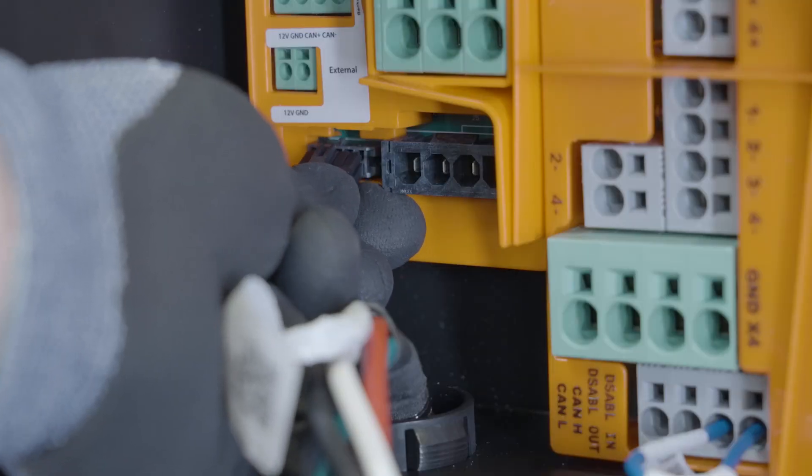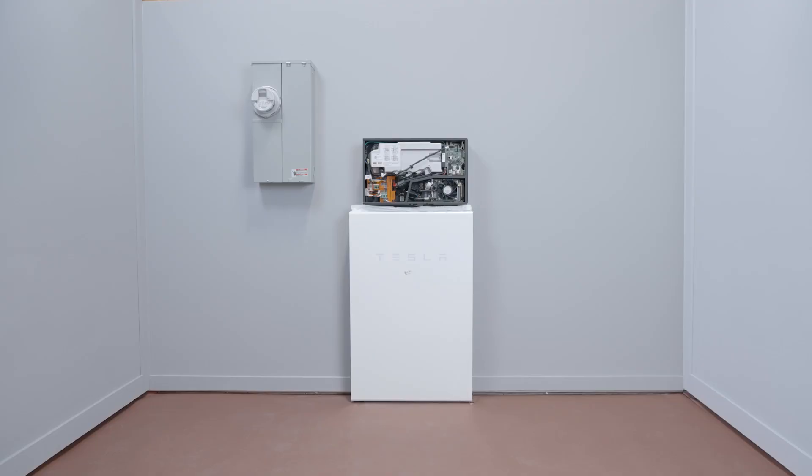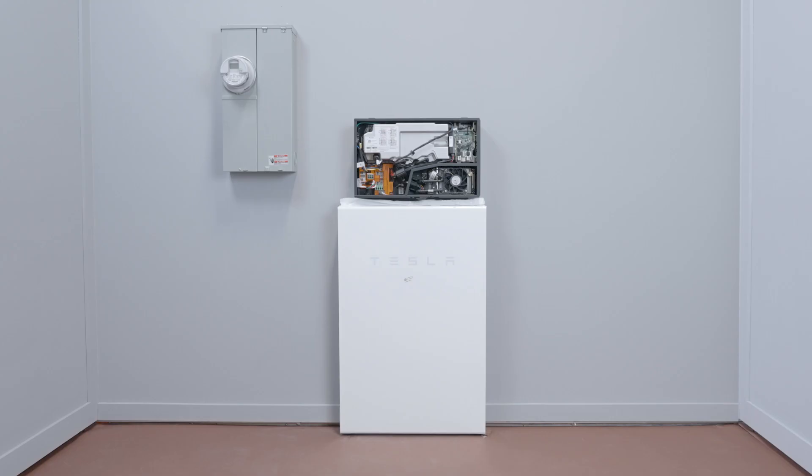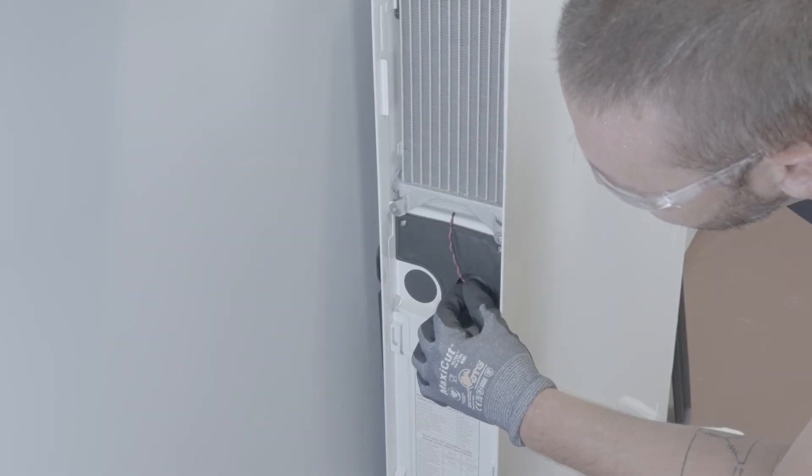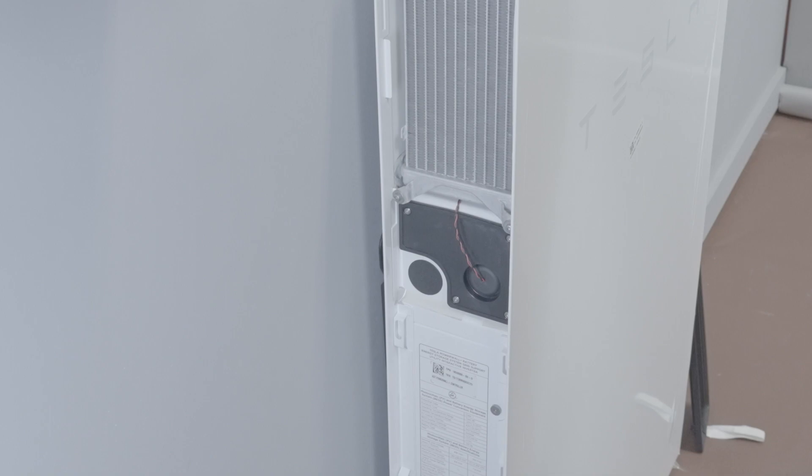Begin by connecting the two harnesses from the inter-product harness into the ports at the bottom of the solar assembly. The other ends of the two harnesses are already terminated inside the battery assembly wiring compartment. When installing a system with a single Powerwall Plus, it is not necessary to open the wiring compartment on the battery enclosure.